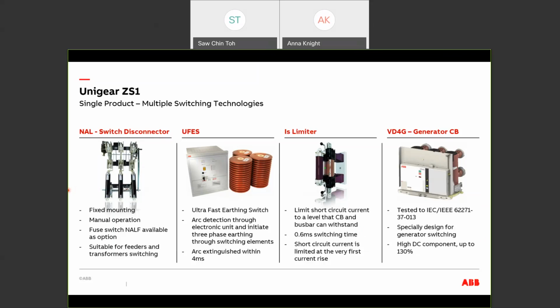The last apparatus is the VD4G. It is actually a generator circuit breaker. So it is to switch generators, as the name suggests, because generator switching normally has very specific functions, and it needs to be tested to IEC and IEEE standards. For ABB circuit breakers, the VD4G, we are one of the first few manufacturers that has been tested to both standards together. These breakers have a very high DC component as well as a very high TRV, the transient recovery voltage, to suit generator switching.